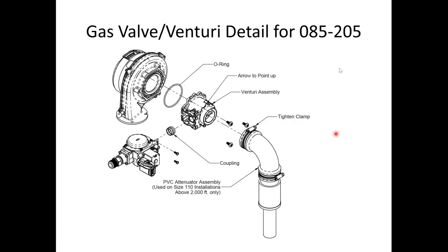So this is showing a detail of how to get the gas valves apart for the 85 to 205. There's going to be a flexible gas connector here, so we technically don't have to take all of this apart. As soon as I get some nicer weather out here, I'm going to be doing a YouTube video on the LP conversion for this, so I'll be up on our YouTube page. Basically, undo the screws, slide the gas valve back out of the way, replace the venturi, put everything back in, and tighten the gas valve back up.